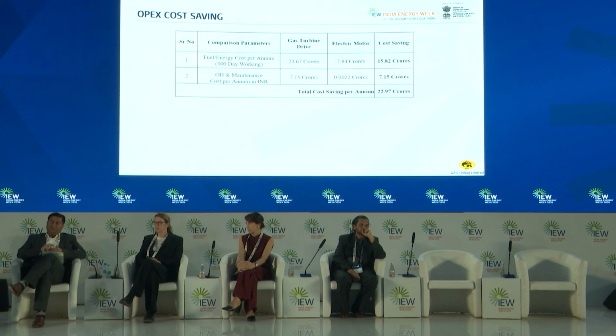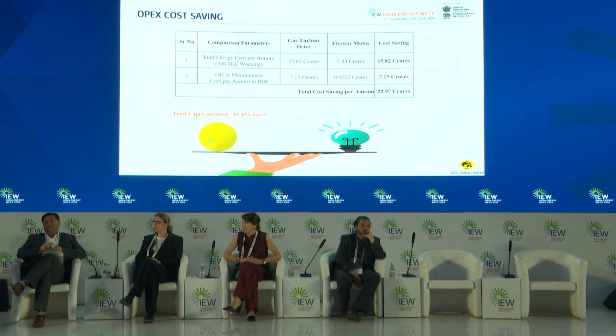Now let's talk about OPEX cost saving. The fuel cost for the gas turbine drive per annum was 23.67 crore. For the electric drive, it comes to 7.84 crores. Overhauling, service and maintenance cost for the gas turbine drive per annum is 7.15 crores, and for the electric motor it is 0.22 crores only. So the cost saving per annum is 22.97 crores. As I said, the total capex involved is 16.45 crores. The per day benefit is 7.66 lakh. The capex of 16.45 is only for the first electric drive, because we already had the substation and grid power was available.